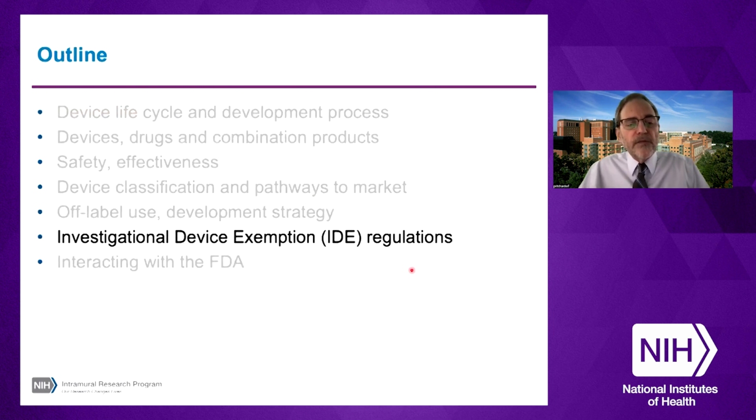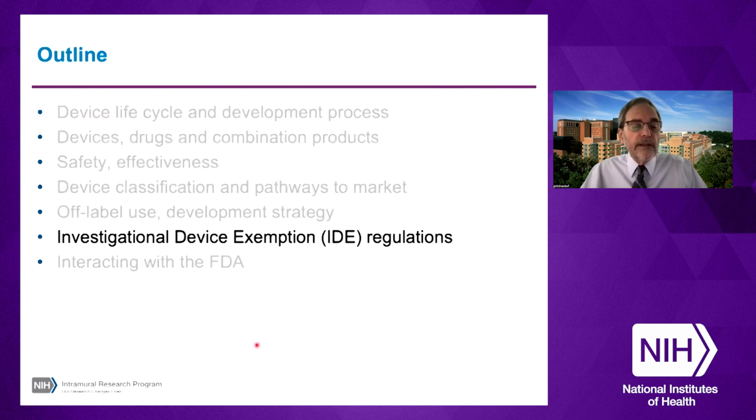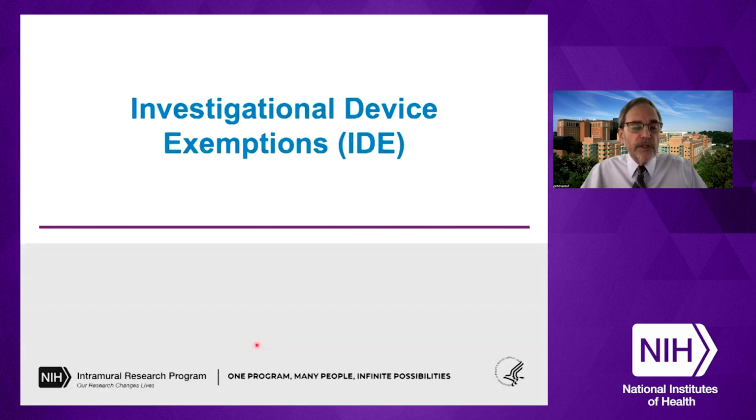So let's talk about the investigational device exemption, or IDE, regulation. Say you're at the point where you need to do a clinical study or want to do a clinical study, then that's when the IDE regulations will come into play. I do want to note up front that this applies equally to manufacturers, like a large device company that's developing a product, as well as individuals, say a physician who comes up with a device idea and wants to test it in one of his or her patient populations.